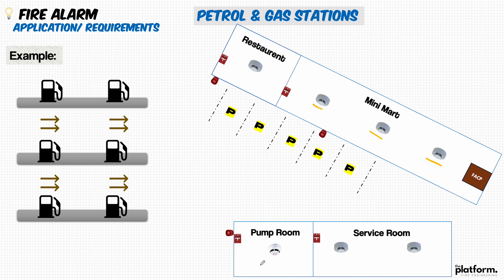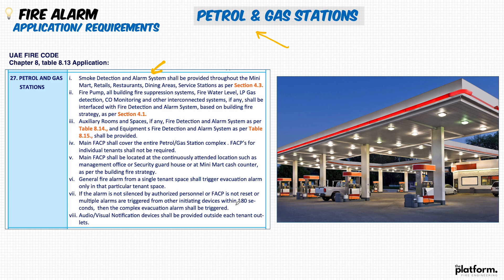In the pump room, I changed the device and installed a heat detector, because as per what we learned in the heat detector lectures, we need to install heat detectors in pump rooms and any area where we have an expectation of smoke generation — to avoid false alarms. Interfacing is also mentioned here, same as in the industrial areas and auxiliary rooms we already covered.